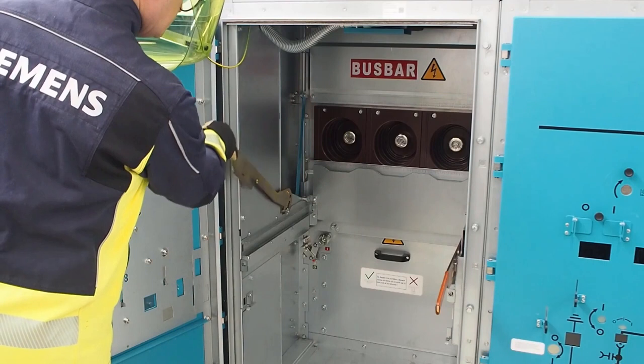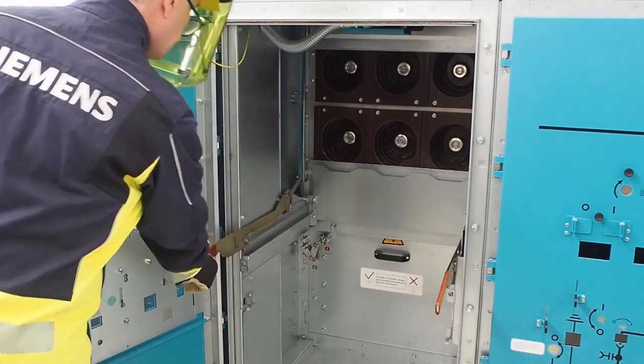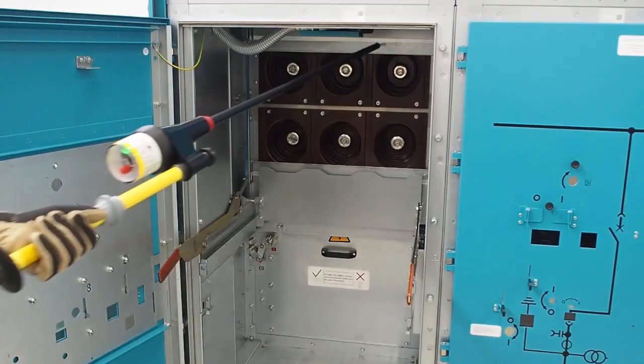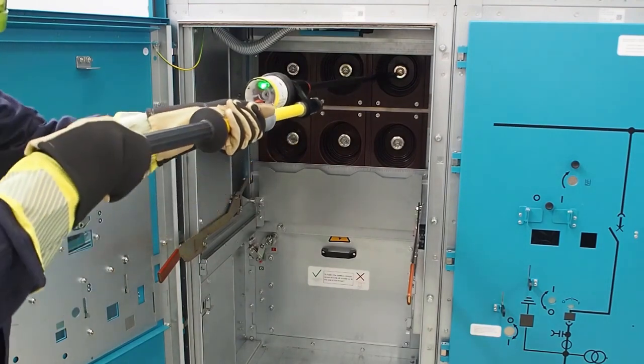Then, open the upper shutter of the bus bar. Finally, check that there is no voltage across the upper contacts of the bus bar.